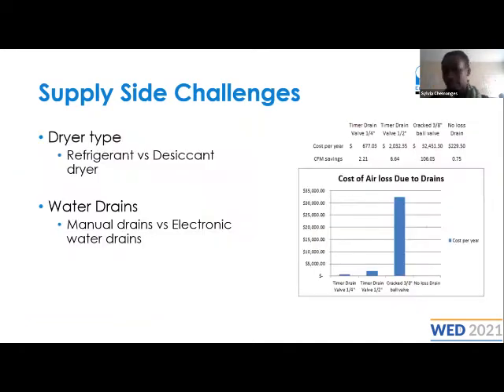Okay, so which other challenges do we face on the supply side? Another thing is equipment selection. For example, you work in the food industry as compared to a company that requires only control air. The energy that is required to make compressed air very dry so that it can be used in a food manufacturing setting would be higher than that used for a control air application. For control air, a refrigerant dryer would work. But if someone considers taking a desiccant dryer to dry compressed air, there's an extra 15% of energy that you will lose to obtain that very dry air, which is not something that you need for control air. So that's another challenge. Equipment selection is usually a big problem.